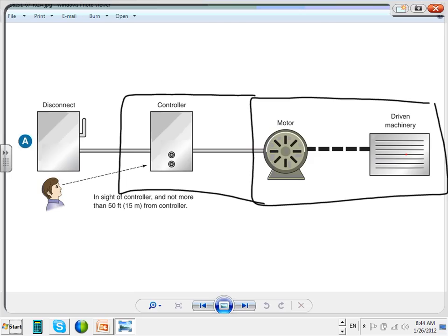Within sight means, as we define it by the code, within sight it has to be 50 feet or within sight. 50 feet, no barrier, so you don't have to jump 10 feet to reach the disconnect. Same level, 50 feet, no barrier in between. Any question, guys, about that particular one, the disconnect? So the disconnect has to be within sight of the controller, the motor, and the driven machine, or you have to have one for each one of them. I'll show you a couple of nice pictures. That's what I want you to take.